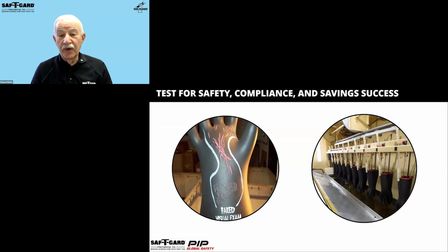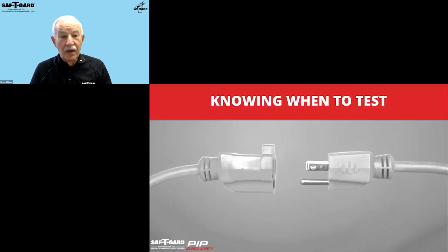The improper use of rubber insulating gloves is a matter of life or death, which is why dielectric testing is a critical and necessary component to maintaining worker safety and compliance. Rubber insulating gloves are expensive, and many times these costs are unnecessarily increased by purchasing replacements that could have remained in service if they were properly inspected, tested, and recertified. Now, you've got to know when to test them.